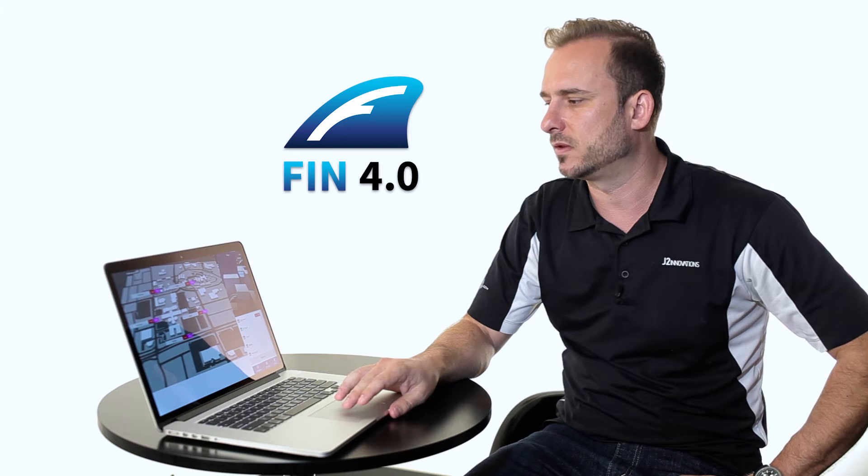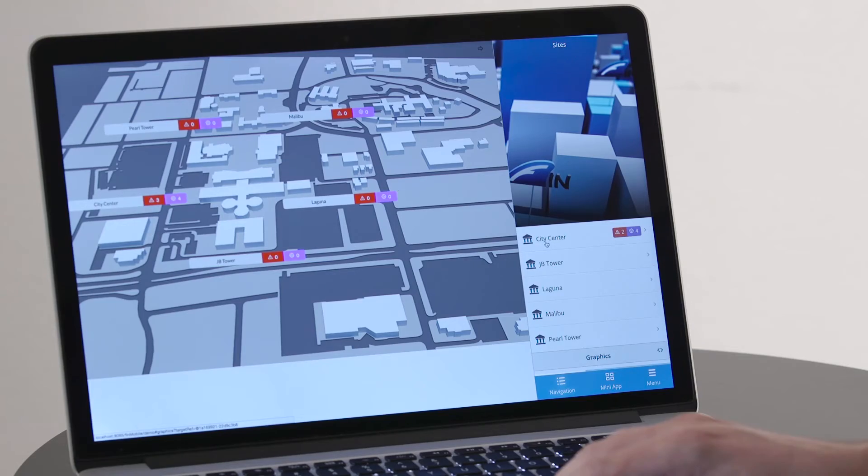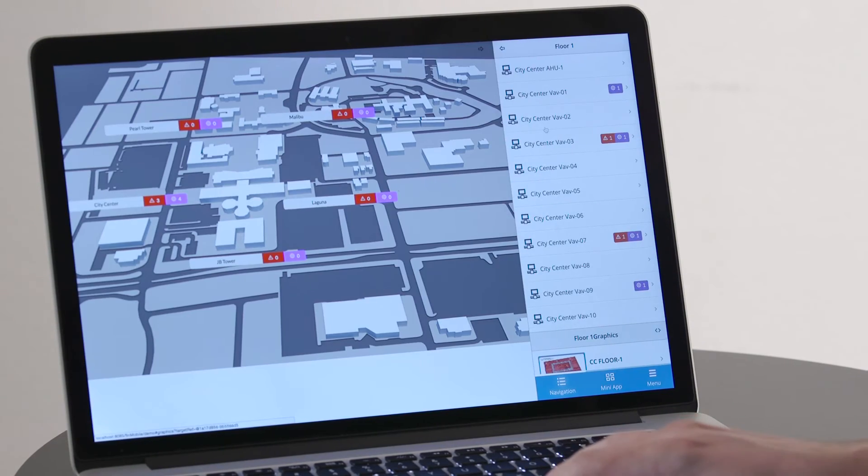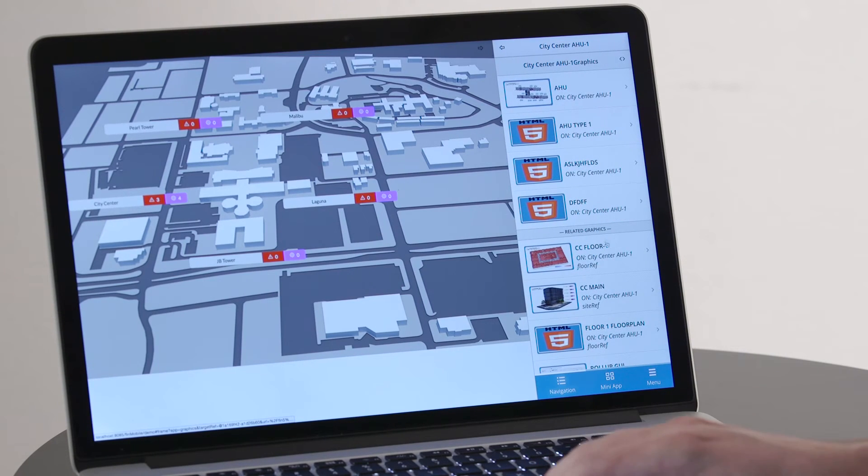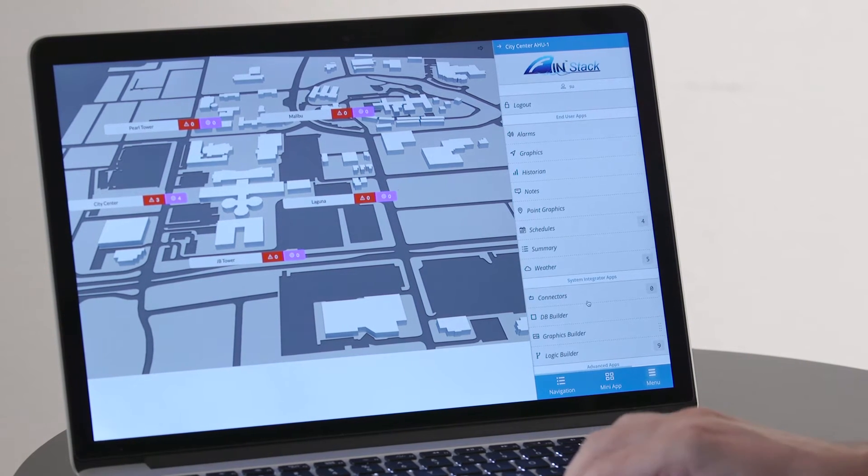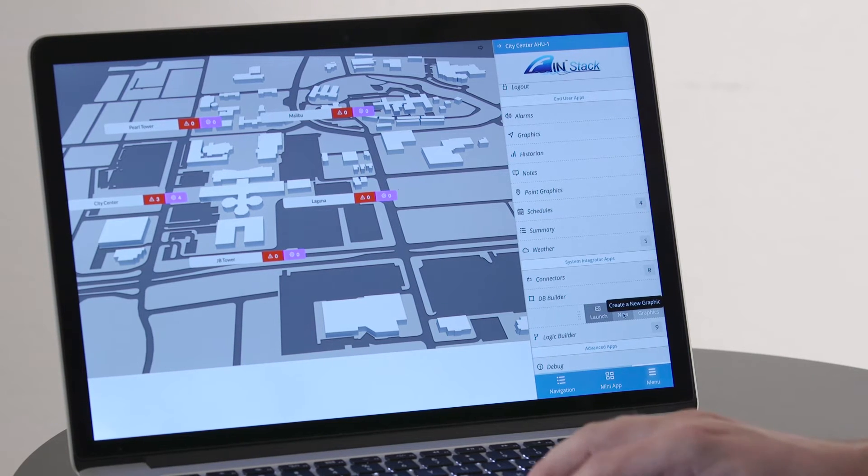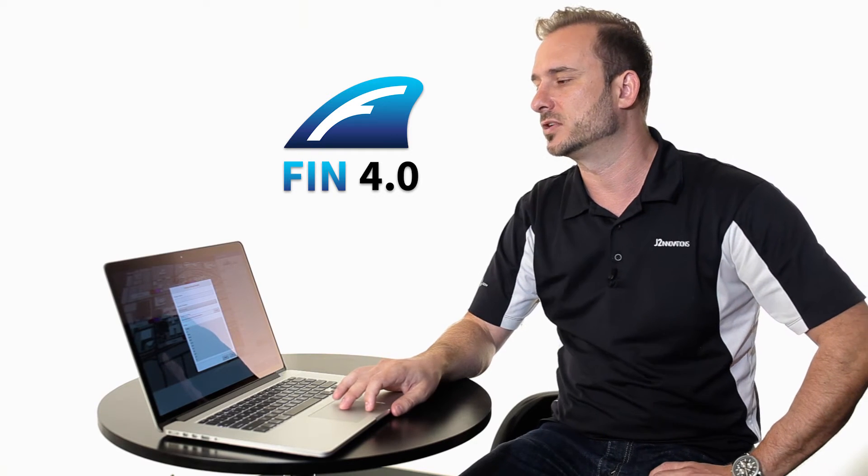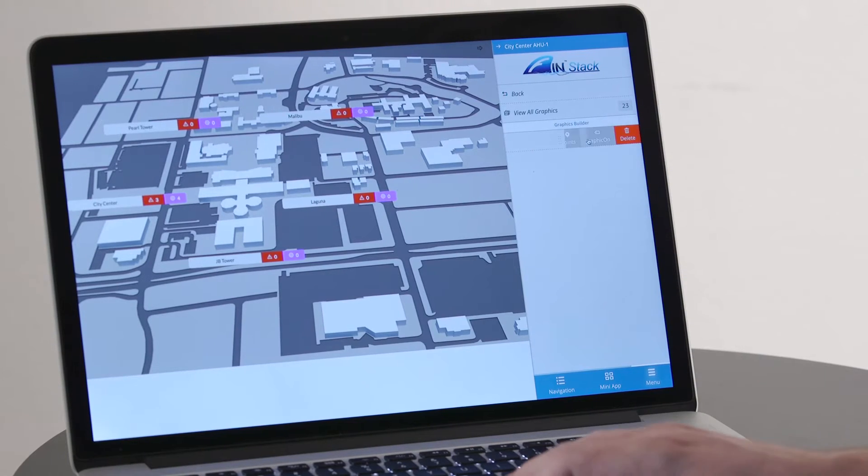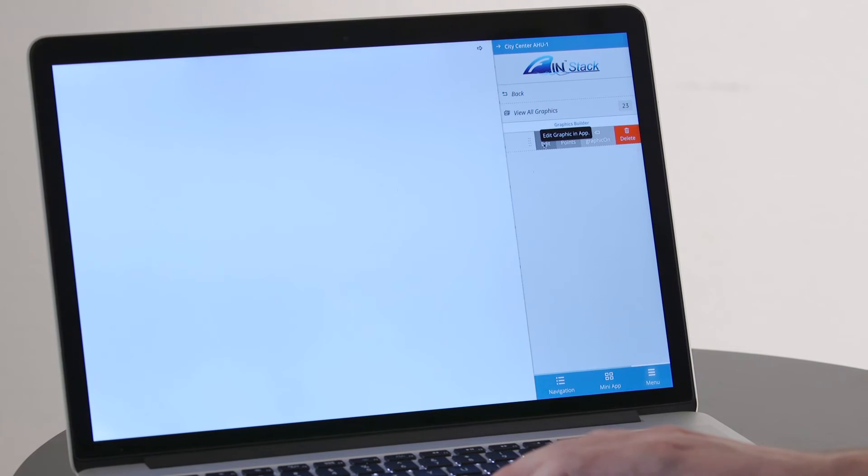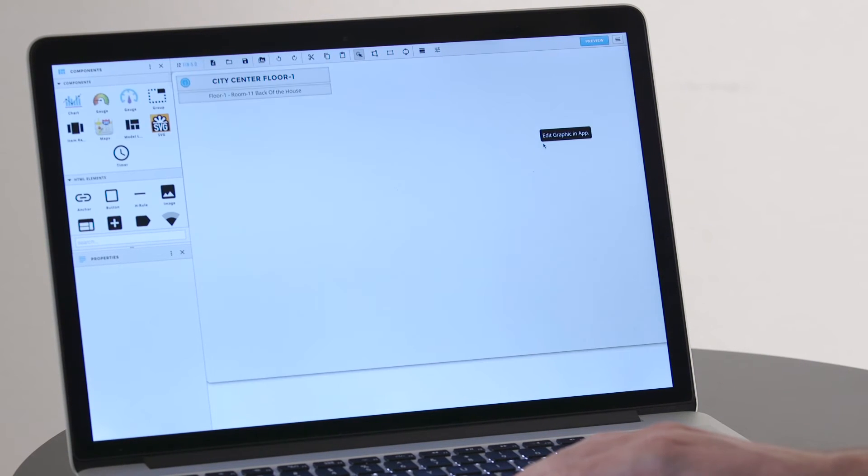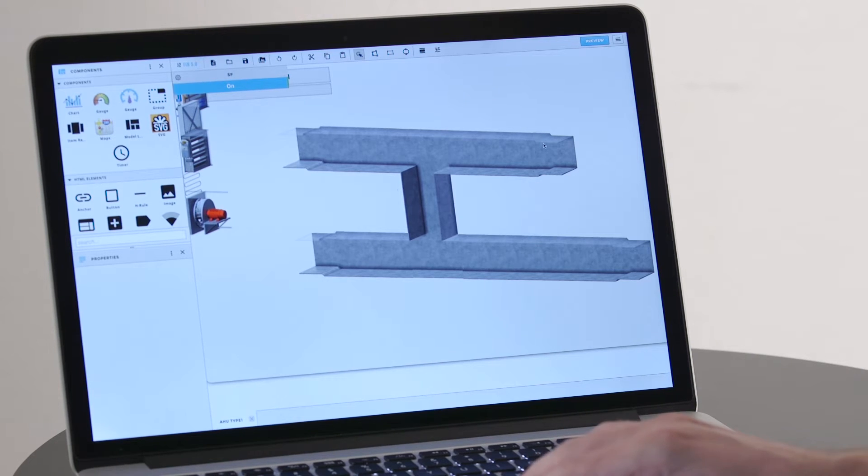Okay, now let's take a look at engineering the job. Remember we changed the workflow 180 degrees. Everything you saw previously in our demo with magic bubbles and things running on the phone can now work automatically for you and this is how you do it. So what you do is you just navigate to where you want to go. So let's go to an air handler and let's go in the Smart Menu and now let's go to the graphics builder and let's hit new graphic. Now we have a wizard that will open up. Let's create our graphic. I'm going to name the air handler and I'm just going to select the points that I want. Now let's go in to edit the graphic. So the wizard that we used to make that, that you just saw, automatically based on the points that I clicked on, tried to guess which objects you wanted to use. Let's go ahead and move those graphic objects around.